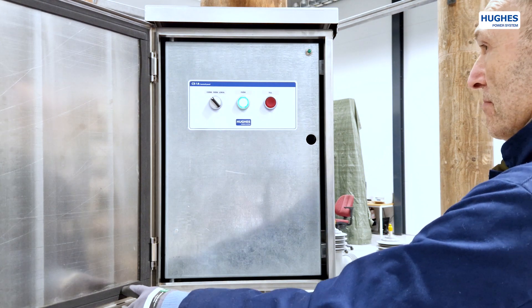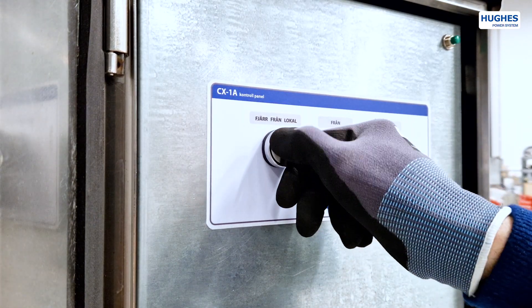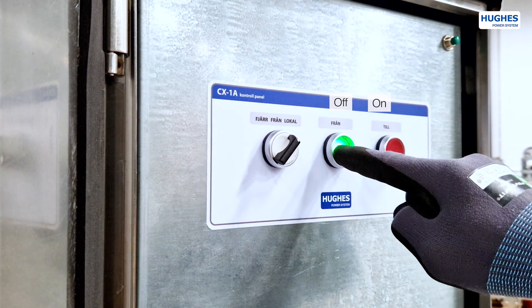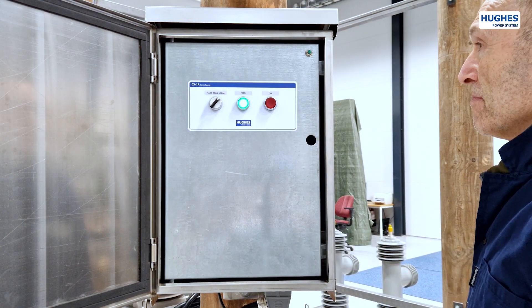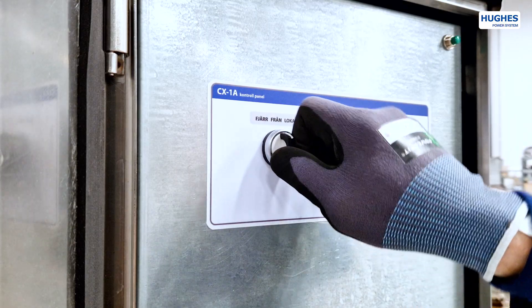The front operating panel contains a rotary switch — remote, off, local — for different modes, and two operating buttons, on and off, which also have indicator functions. Like all other Hughes cabinets, the CXB has a door alarm switch which activates when the door is opened and sends a signal to the SCADA system, notifying about access to the cabinet.